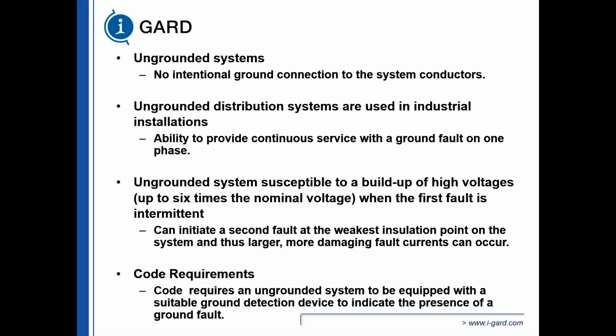So normally a ground detector would consist of 3 incandescent lights. And when the system is healthy, all 3 lights are on with the same brightness. When you have a ground fault, the light on the faulted phase extinguishes because there's no potential difference. The faulted phase and ground are at the same potential, and that potential is 0. We don't energize the ground conductor when we have a ground fault. What we do is shift the vector relationship with respect to ground such that the unfaulted phases are at 480 volts, so you get 2 bright lights and 1 light that's out. So the 1 light that's out indicates that you have a ground fault. Unfortunately, it's a poor method of detecting ground faults because there's no difference between a burnt out light bulb and a ground fault.